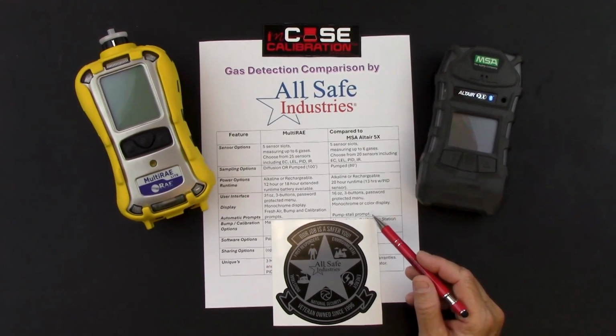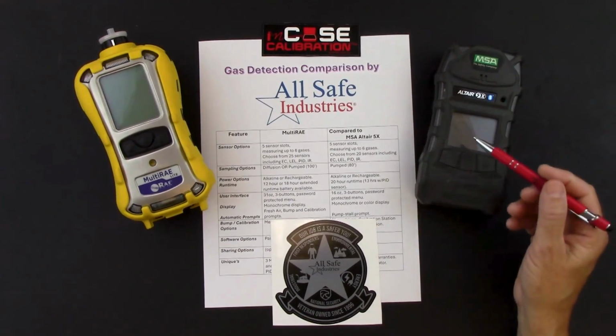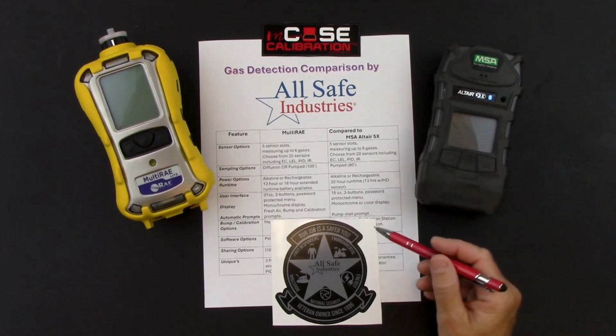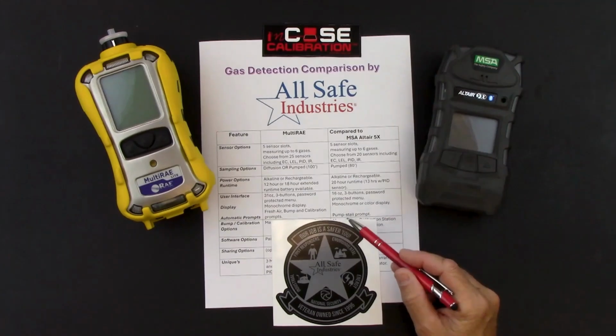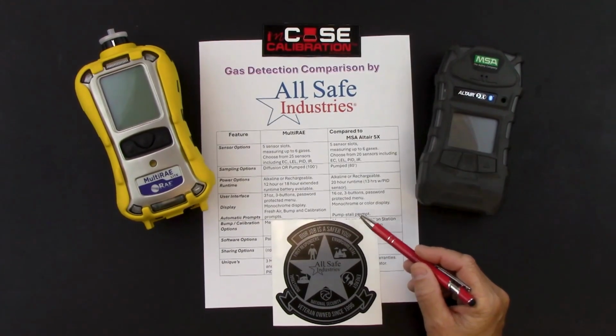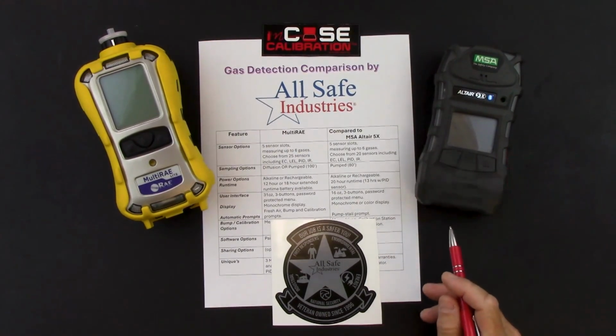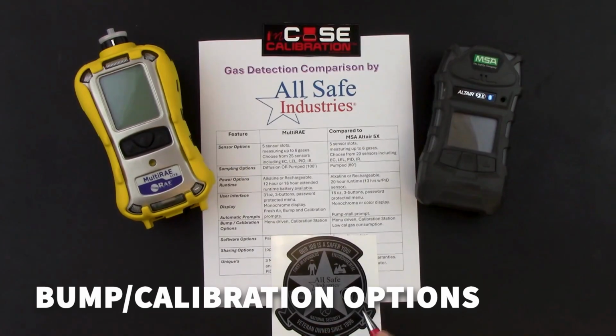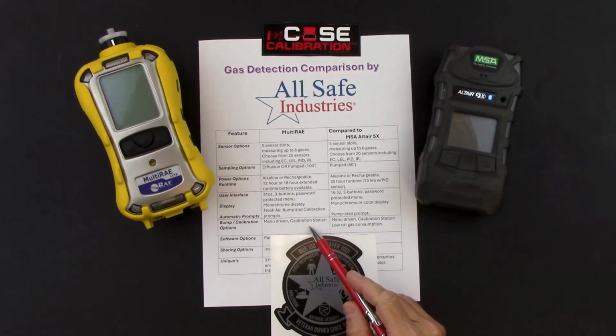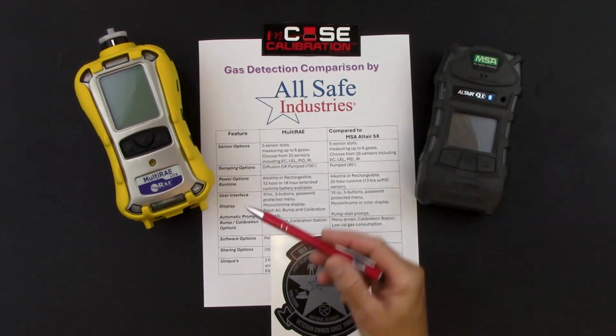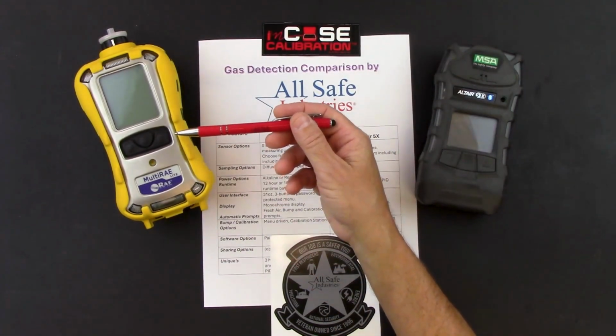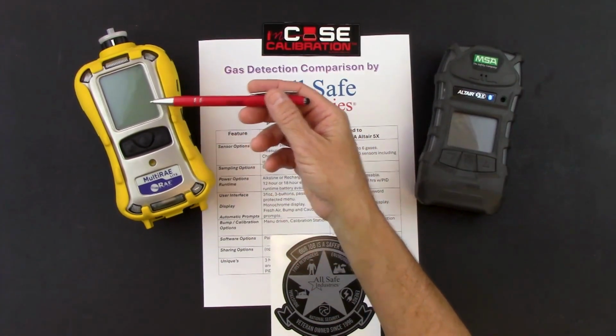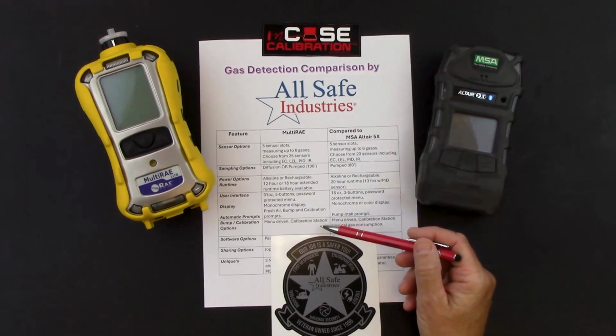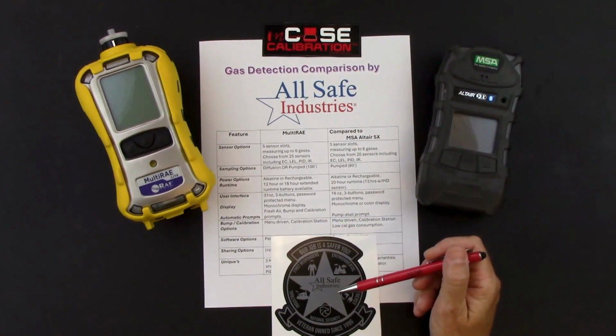Kind of a neat little feature there if you want to spend the money on having your logo on your meter. And then the prompt that we get from the Altair 5X, and it happens every time we power up the instrument, it's going to prompt us to do a pump stall just to confirm that the pump is working properly. Our bump check and calibration options, we have menu driven and calibration station for the MultiRAE. So we can run a bump check, we can run a calibration by getting into the menus of the MultiRAE, or we can use the AutoRAE 2 calibration station to run those bump checks and calibrations.